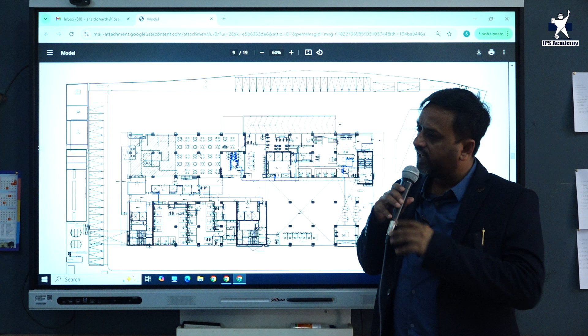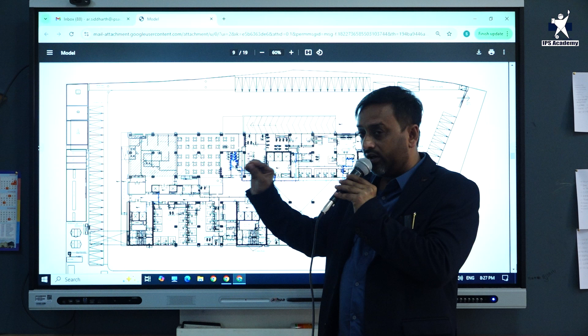Every floor comes with all the planned utility areas, not just OPD floors. It is so well planned that you have clean utility, dirty utility, AHU rooms, linen storage, toilets, and DAT at all levels, not just at one level. All shafts are coordinated so that dirty things are not traveled from one floor to another. Every floor is provisioned with these rooms, around 80 to 100 square feet each. These are the must-have spaces that all architects must consider when planning a hospital.